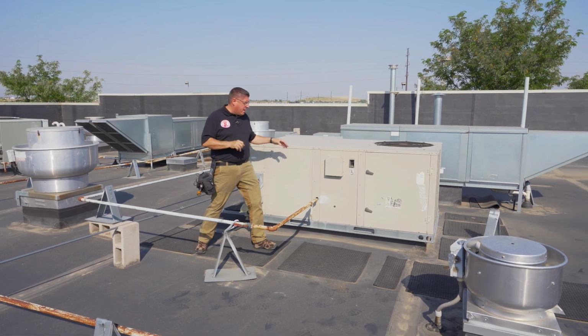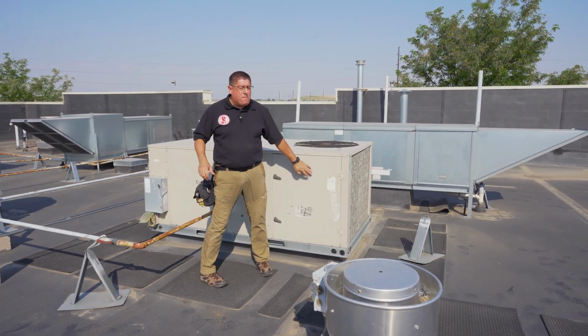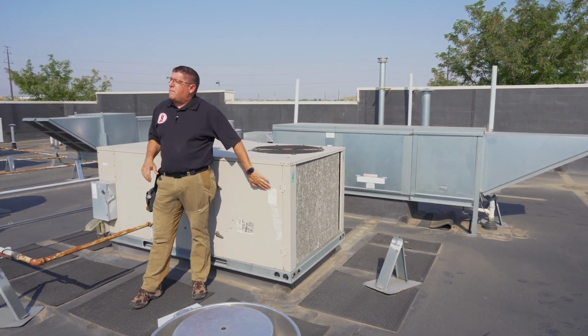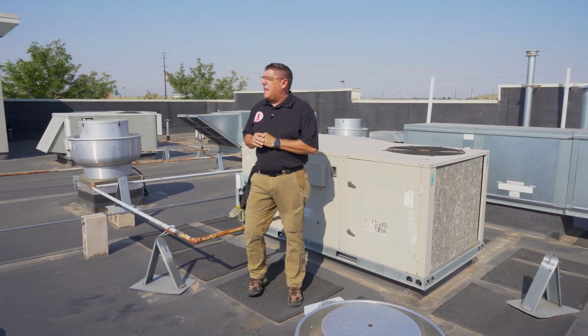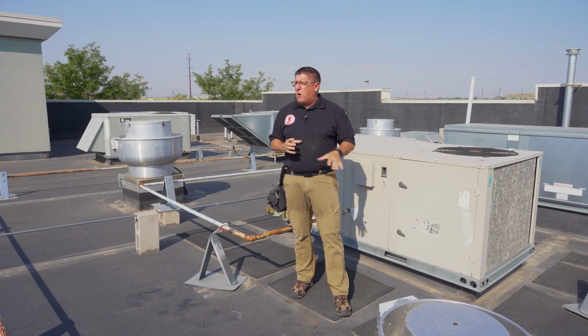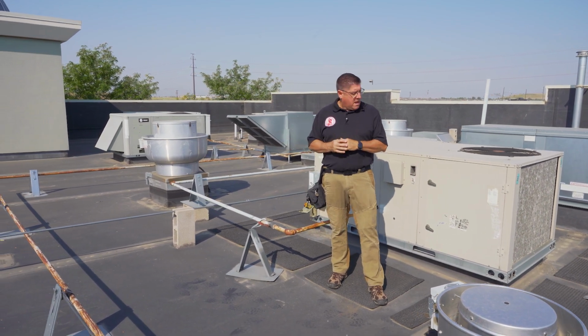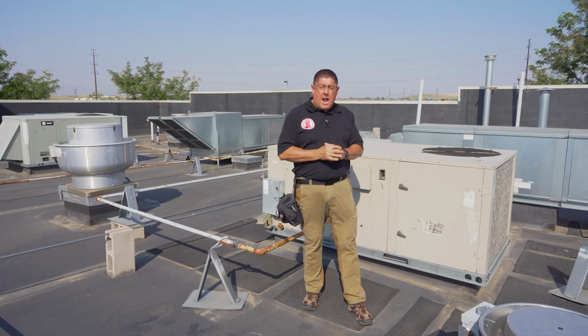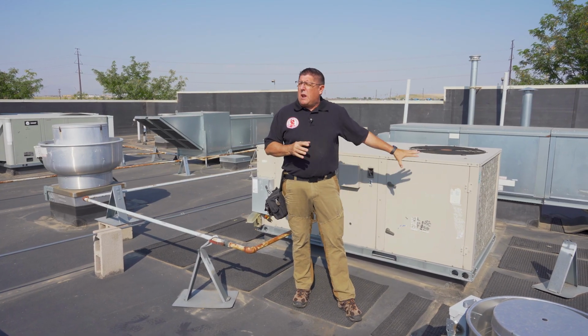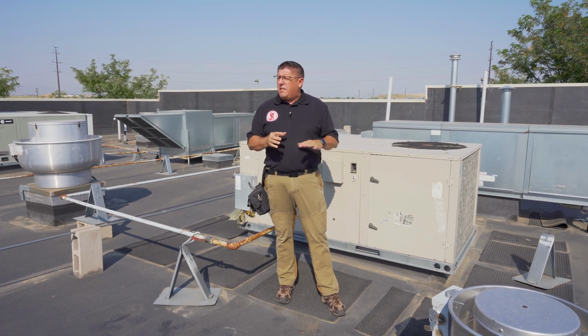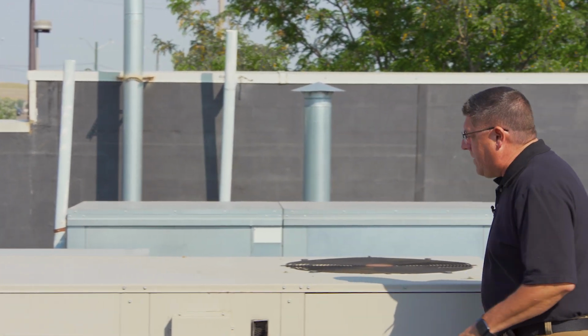The next thing you want to do is identify how big it is, what the age is, and what the manufacturer is. That would be noted with the label plate. In this particular case, this label plate has been worn off to the point that it's illegible. So I would want to document that on my report with a photo saying illegible label plate. And then I would make my best guess of how old this appliance is. This appliance is probably 15 to 20 years old, judging by the wear and tear that's on it. So we would want to make sure we identify that and let your client know that that was only a professional estimate and not the exact date that would be present on this.